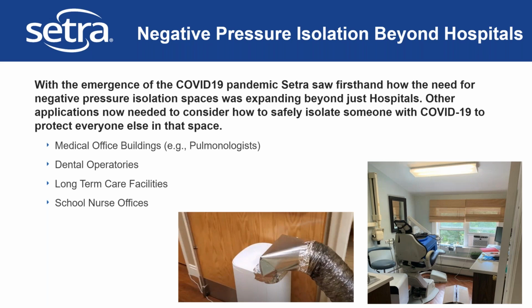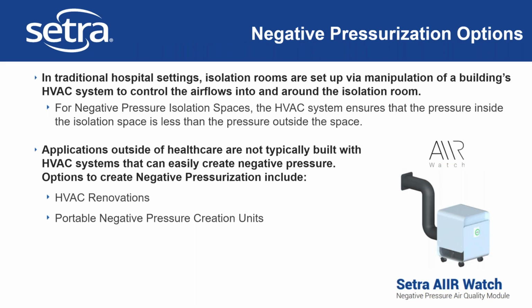We saw firsthand how negative pressure expanded beyond just hospitals. Because we kept getting these inquiries, we started talking to more people across these new applications to discuss what a solution would look like in their space. In traditional hospital settings, isolation rooms are set up using the building's HVAC system, manipulating airflows with full controls, because that's how they were designed and installed. The HVAC system ensures the pressure inside the space is less than the pressure outside.